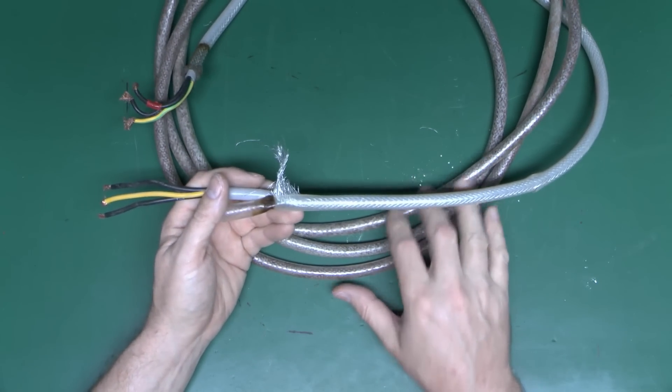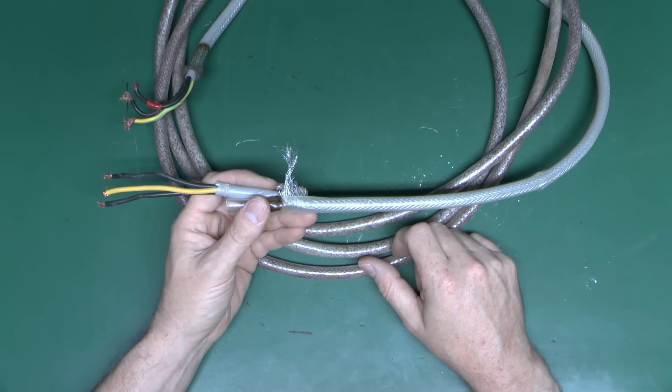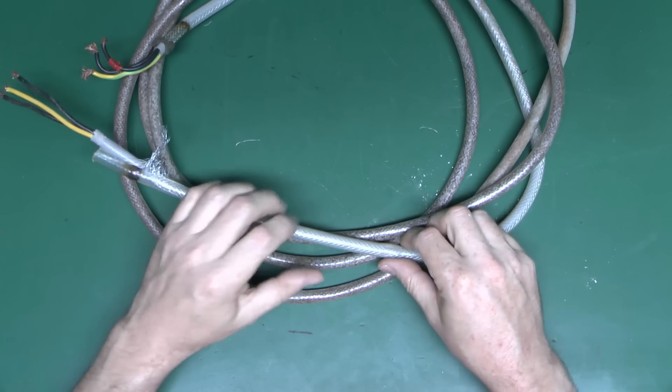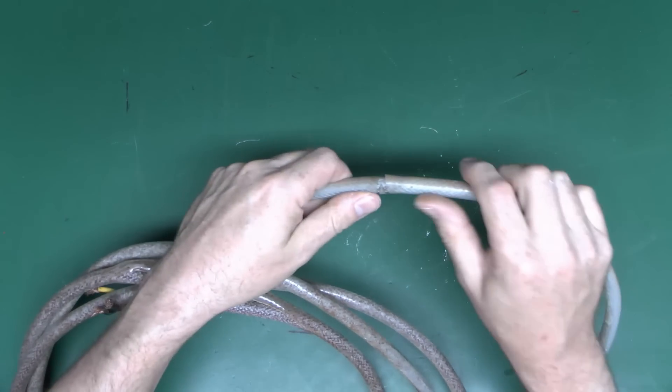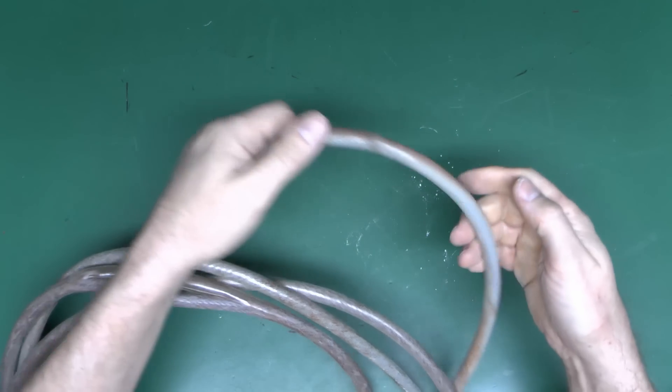It's not suitable to use outside. It seems to be a popular thing on installations like air conditioning where this is trailed all over the roof in a disgusting spaghetti mess. But of course that doesn't work either, because then you get this degradation and damage here. And of course it falls apart within only a couple of years. And you can see over this side where there's cracking and breakage has occurred, because this is the part which was above ground.